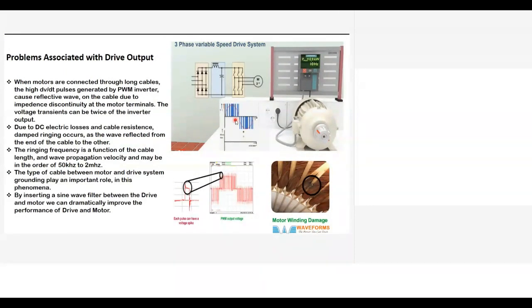When this is routed through a long distance cable, the cable has a capacitance effect, and the motor will have a reflective wave because of its winding. So they interact and cause high dV/dt pulses. These dV/dt pulses can be 2x or 3x, depending on the severity of the pulses. So when motors are connected through long cables, the high dV/dt pulses generated by the PWM inverter cause a reflective wave on the cable due to impedance discontinuity at the motor terminal. The voltage transition can be twice the inverter output. It can be much more also.